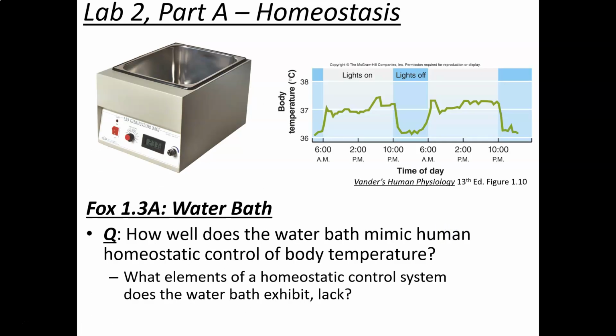If you remember, in the first video we talked a little bit about the water bath. The water bath is what they call a constant temperature water bath, and water baths are used to keep the temperature at a stable point. Water baths, in the vast majority of situations, only have a heater, and there are a bunch of reasons for that. One is price. A water bath with both a heater and a cooling mechanism costs at least 10 times more than a water bath with just a heater, and they're not really practical.